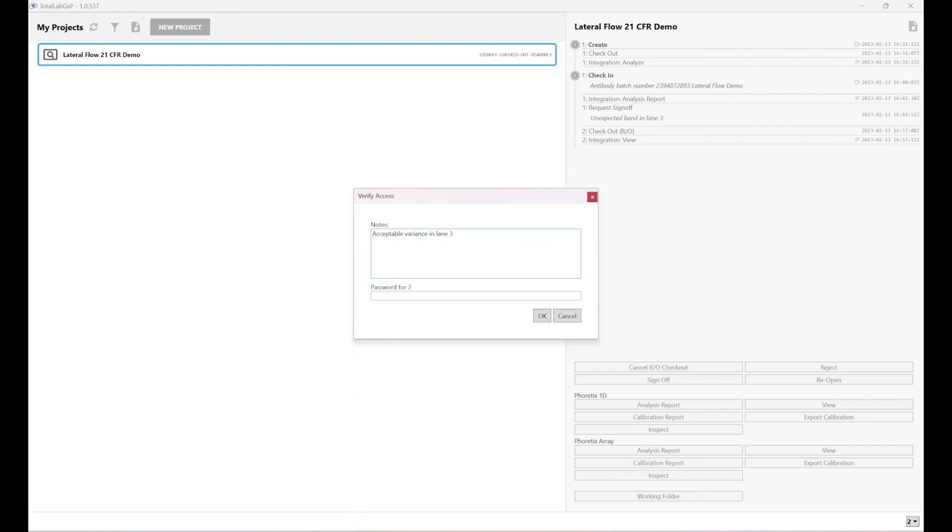When someone comes in like the FDA to audit your site, for every project that's been analyzed, they can see that there's been this conversation about whether it's going to be accepted or not. The analysis has been performed in line with the SOP and things like that. This is the area where you can put any notes like that. And before I can sign it off, I have to put in my password for my user that has my sign off permission. This again is a security feature that prevents, if I, as someone with the power to sign off projects, had stepped away from my desk, but I'd stayed logged in, no one else can come and approve projects that I personally haven't looked at or been able to approve.